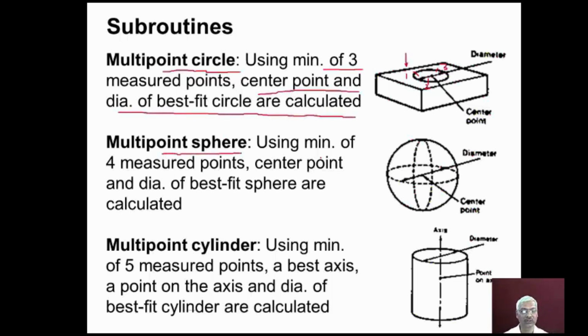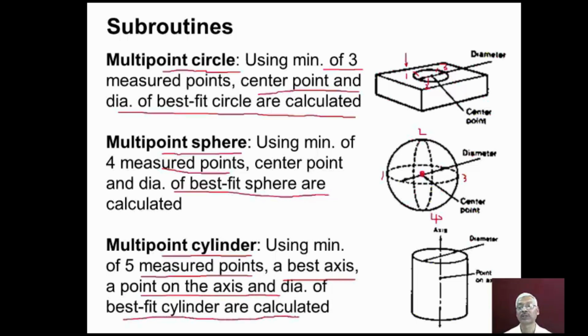and multi-point sphere using a minimum of 4 measured points. So 1 point here, second point at this place, third point at this place, and fourth point at this place. Using a minimum of 4 measured points, the software can calculate the coordinates of this center point, and then the diameter of best fit sphere can be calculated. Multi-point cylinder using a minimum of 5 measured points, a best axis, a point on the axis, and diameter of best fit cylinder can be calculated.